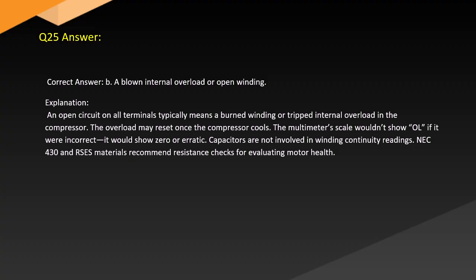Answer. Correct answer: B. A blown internal overload or open winding. Explanation. An open circuit on all terminals typically means a burned winding or tripped internal overload in the compressor. The overload may reset once the compressor cools. The multimeter's scale wouldn't cause this; if it were incorrect, it would show 0 or erratic readings. Capacitors are not involved in winding continuity readings. NEC 430 and RSES materials recommend resistance checks for evaluating motor health.